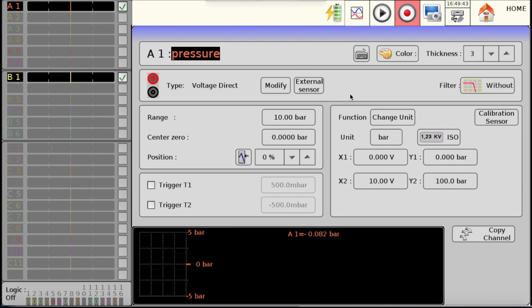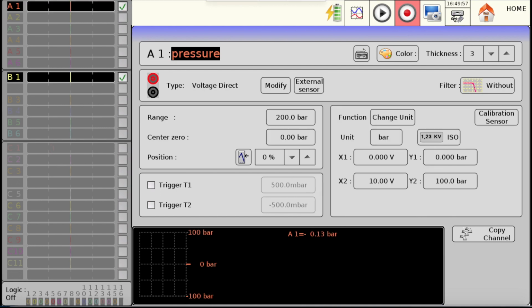Our display range being from 0 to 10 bars, we realize this is not enough since we have set a Y2 at 100 bars. So we need to increase the range to 200 bars, for example. Now let's set the center 0. The 0 being in the center, we have a display from minus 100 bars to 100 bars. So we will set the 0 at the minimum value to have a display from 0 to 200 bars.